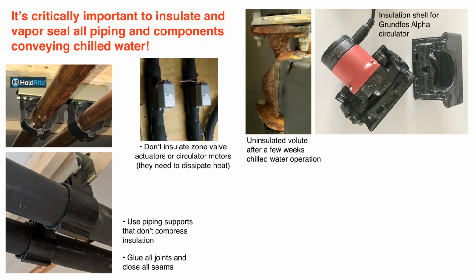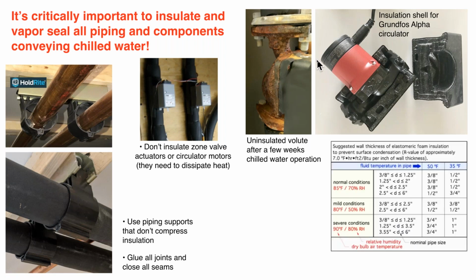Grundfos does make a small circulator. They do have the option of an insulation shell. If you use that, make sure you not only put the shell together, but you caulk all the seams. Remember, the idea is to keep the ambient air away from anything that is being cooled down in the chill water system. And the insulation shell, you can see here, does not go up over the motor. Never insulate the motor can on a circulator.